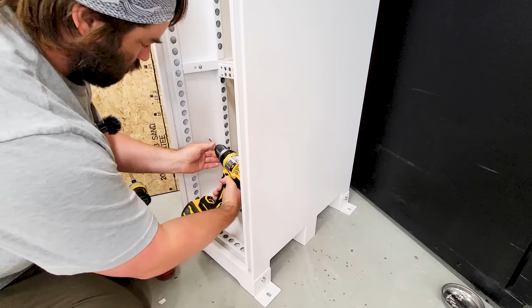In my situation, I'm going to use this 2-inch 90-degree fitting. It's a liquid tight fitting, meaning right here where this goes through there's a yellow gasket, and that gasket prevents rainwater from getting into the cabinet. This is the fitting I'll be using, and it'll be a tight fitting because I'm putting another battery cabinet up against this one, so I don't want it coming out too far. This 90-degree fitting will keep the wires tight to the box.